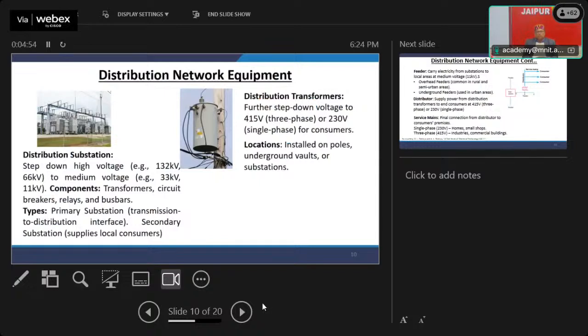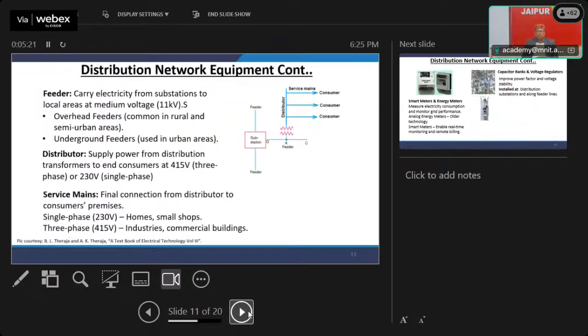Similar to transmission system, in distribution network also we have many equipments. One is your distribution substations, and we do have relays, breakers, bus bars, am I right? And then distribution transformers. Have you seen a distribution transformer? The small cylinder like a water heater, being hung like a structure. Further step down is 415 to 230 volt. Next, please. They are mostly installed on poles.